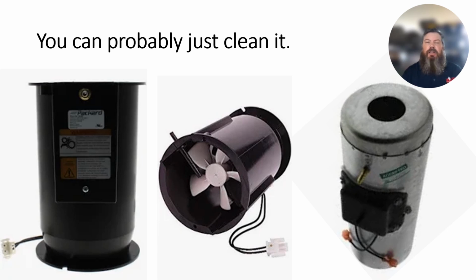A lot of these combustion air blowers are just small inline fans mounted inside these tubes, almost like a refrigerator fan motor, just a small plastic blade. In the off season, all summer long, they get a lot of dirt and debris down in there, and they see a lot of moisture.